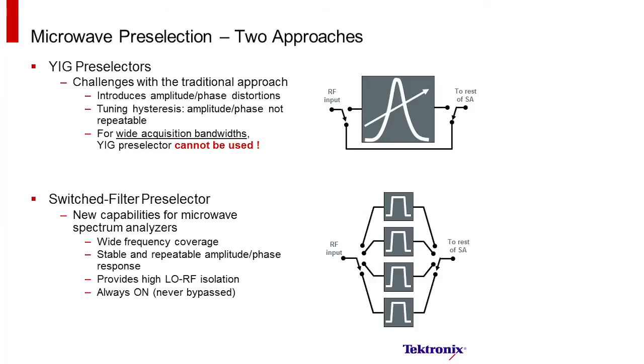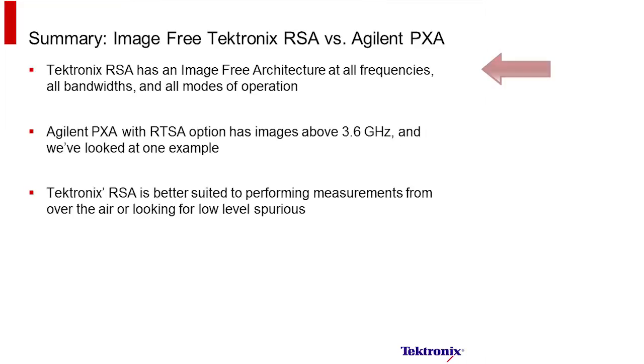The Tektronix RSA uses a switched filter preselector, which gives better capabilities when performing wideband analysis because there's no longer a concern about seeing image frequencies or image signals that aren't really present that are actually created inside the analyzer like the PXA does. With the RSA, you have a stable amplitude and phase response and better local oscillator isolation, and they're also always on, no matter the mode of operation. So Tektronix has an image-free architecture at all frequencies, all bandwidths, and all modes of operation.